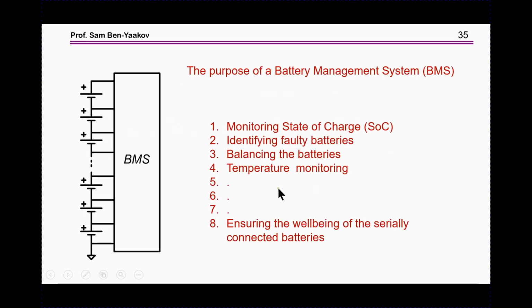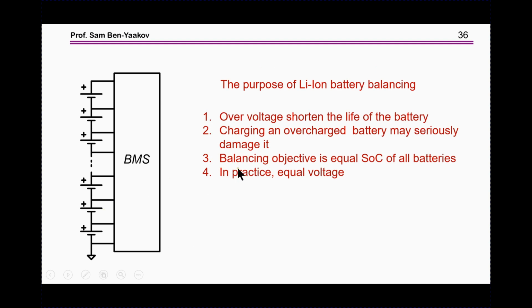The purpose of the battery management unit is, first, monitoring the state of the batteries to see how they are doing and if there is a failure. Another major task is to balance the batteries. The reason is that in a lithium-ion battery, which is very common today, overvoltage will shorten the life. That is, if the battery is overvoltage or fully charged and you still keep charging it, it shortens the life, damages the battery, and also it could be dangerous.